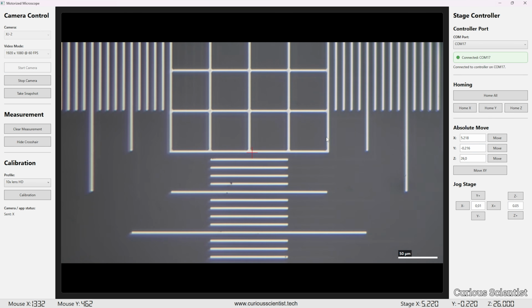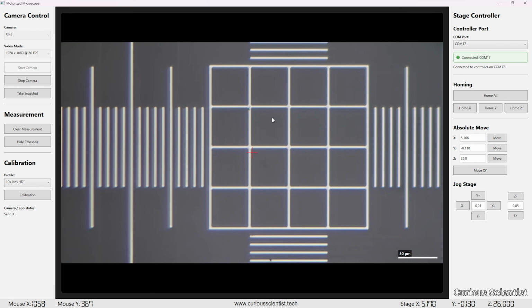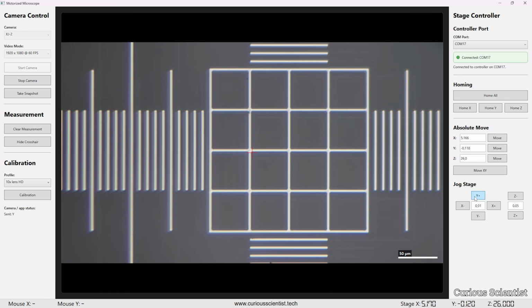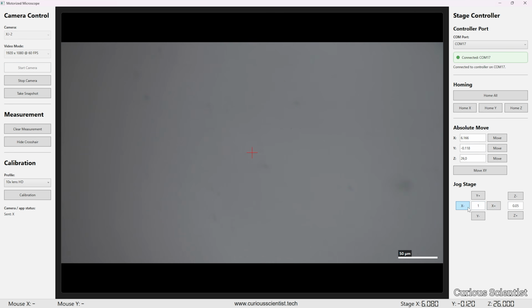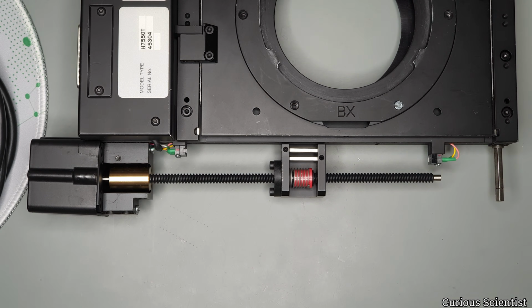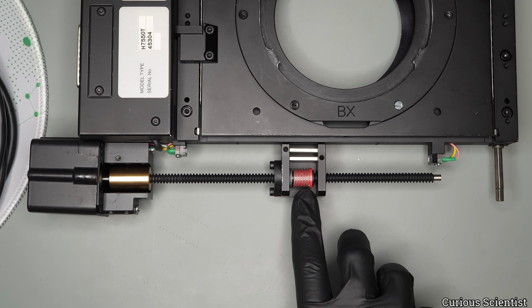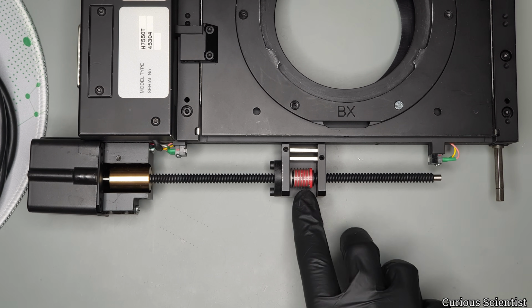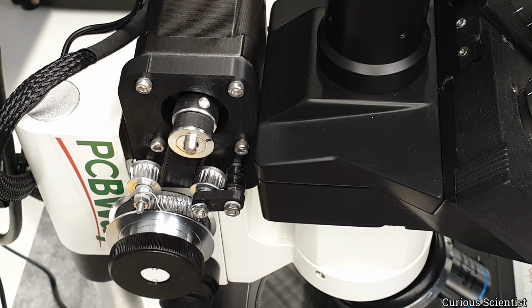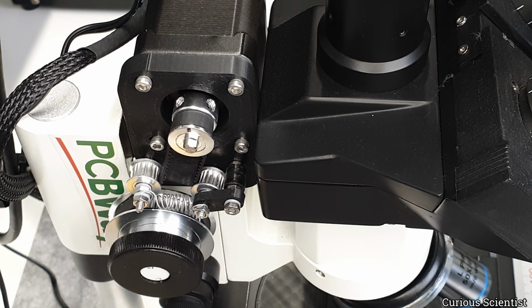They are updated as the stage is moved, and they are getting the values from the stepper motor drivers based on the positions in step units. At the fundamental level, the distances are defined in step units. Then, they are converted into millimeters later. For the X and Y axis, this is done based on the pitch of the lead screws in the stage and the microstep resolution of the driver.